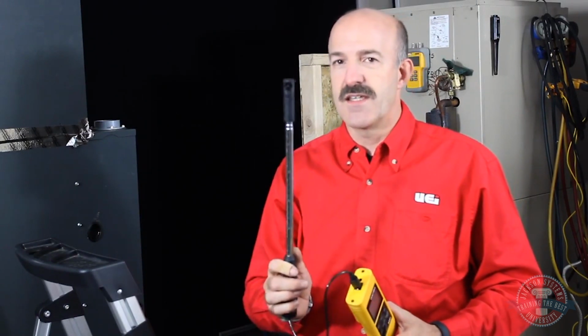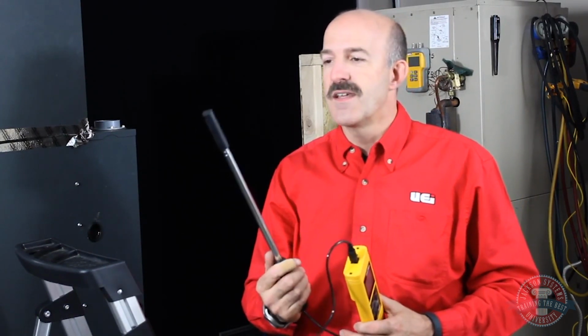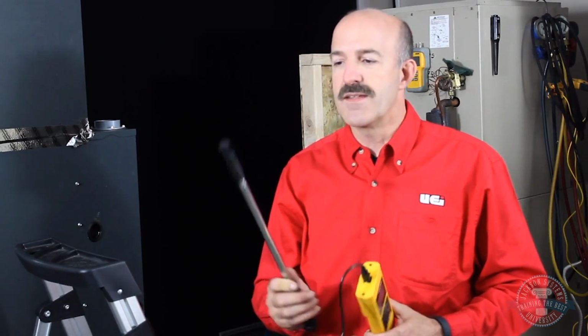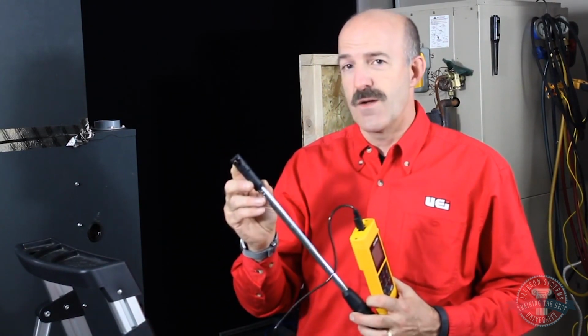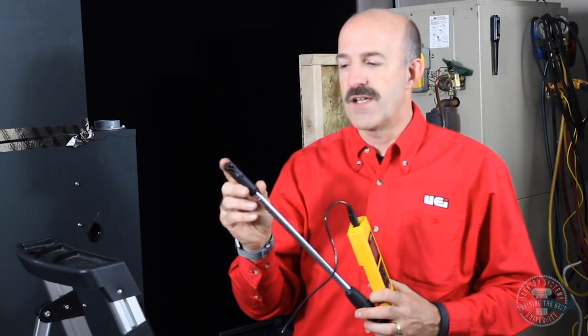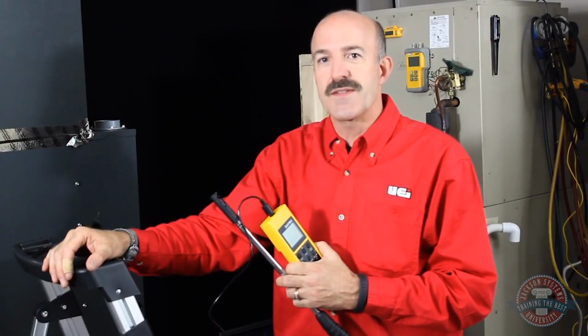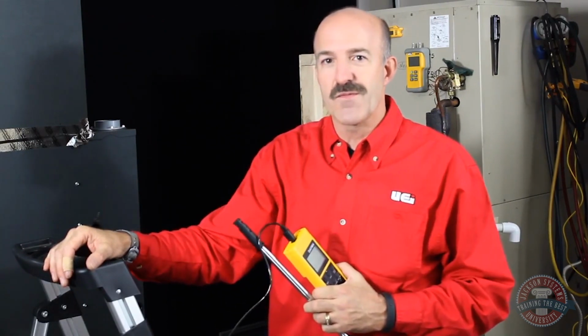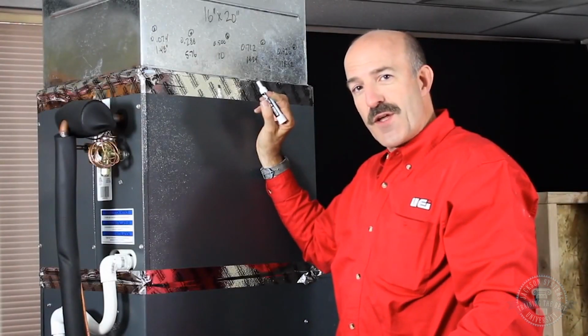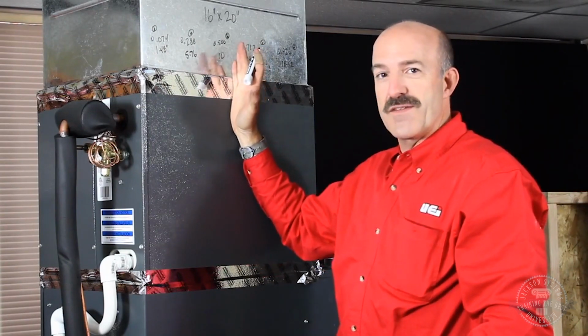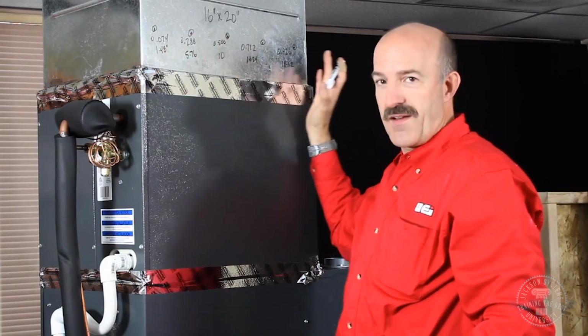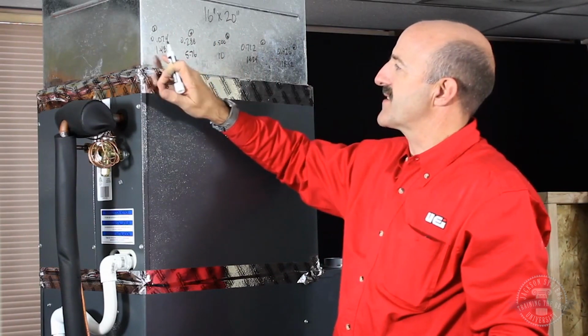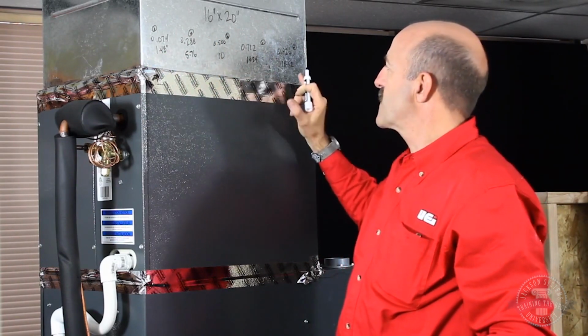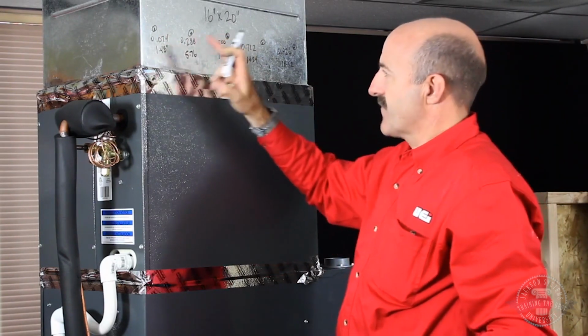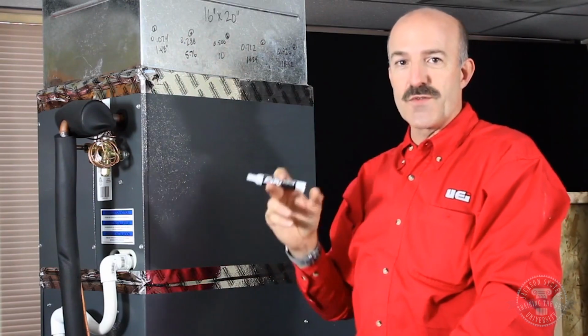Some of the benefits that an induct vane anemometer has over other technologies is it's more accurate than hot wire and more rugged. The key to this, though, is it combines relative humidity with the velocity and temperature, giving you all the measurements in one tool. Next, we'll be preparing the site where the measurements will be taken, drill some access holes, and then work with the DAFM4. This is a 20-inch duct, and on page 8 of the user guide, we recommend 5 holes, and it gives you the spacing. I've already calculated it out: 1.5 inches, 5 3/4, 10, 14 1/4, and 18 1/2. These are my spaces. I'll drill those access holes, and we'll begin taking measurements.